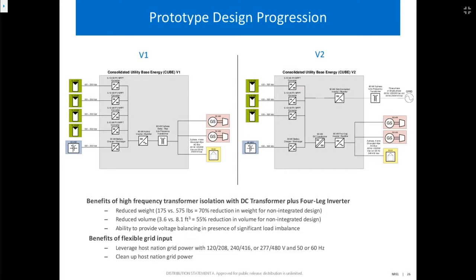But basically, to overview this V1 architecture, PV array inputs plug into four max power point trackers on board the cube. Those handle converting the DC to DC into the system DC bus voltage, as well as a battery that you can plug in, which has a battery charger/discharger inside the cube that interfaces with and is controlled by the overall cube control architecture system. In V2, the main thing added was a high frequency transformer.